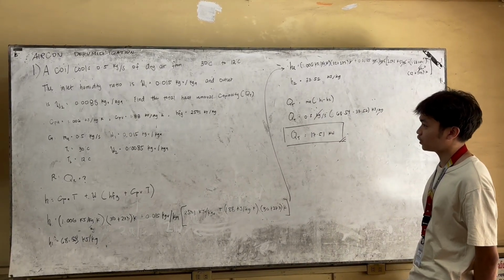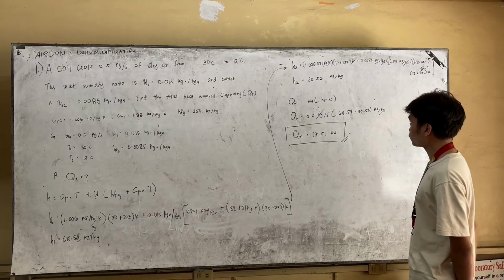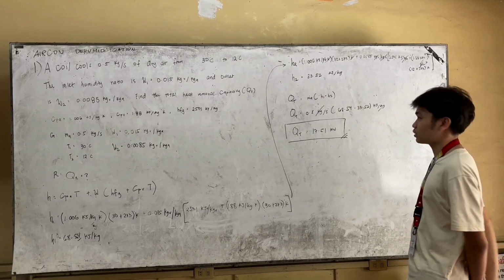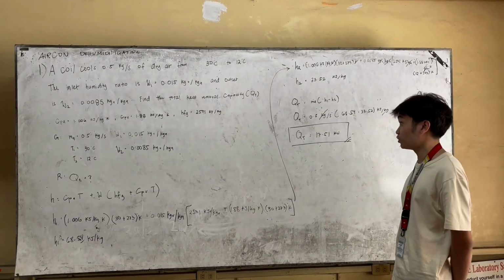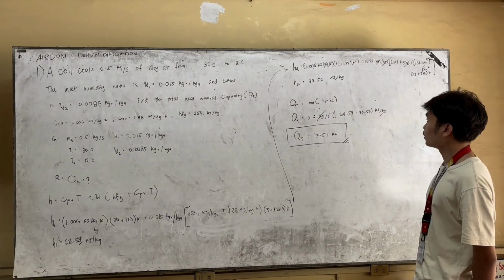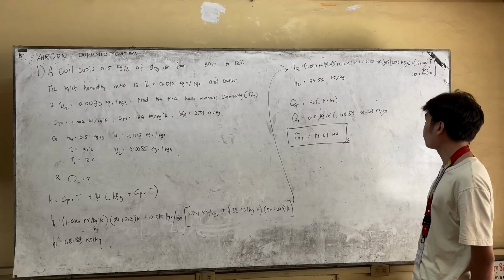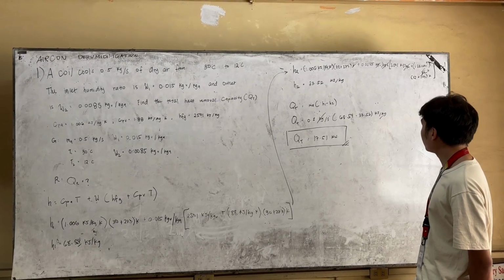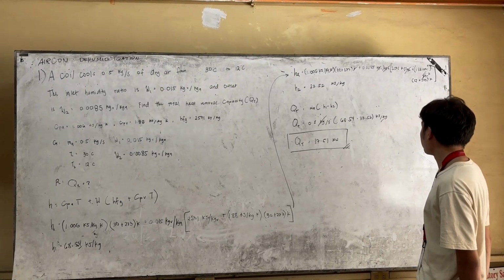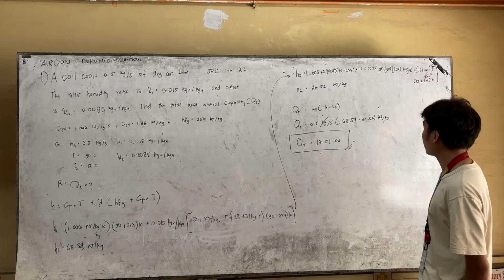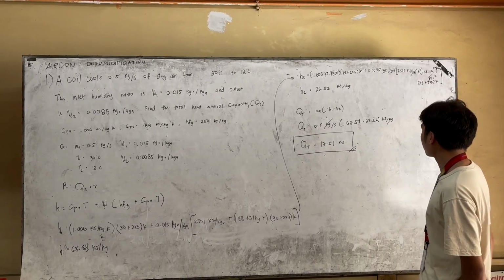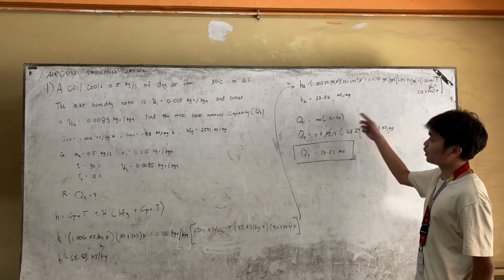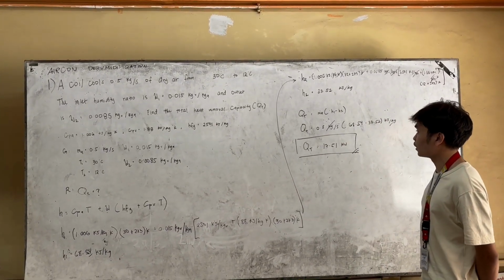same value. We need to plug in all the values at point 2. So we have 1.006 kilojoules per kilogram Kelvin. Then 12, since at point 2, the temperature is 12 degrees Celsius. And we have the humidity ratio at point 2, which is 0.0085 times 2,501 HFG, the value. Then the Cp of the vapor, which is 1.88, times the temperature at point 2, which is 12 plus 273. We need to make it to absolute temperature. So multiply them all, you have 33.52 kilojoules per kilogram.